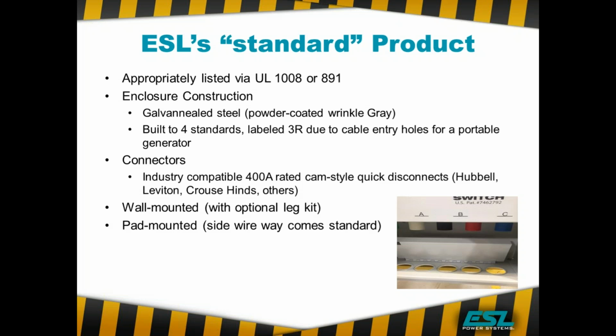Your pad mounted units come standard with a side wireway to bottom feed, since with most pad mounted units the conduit is going to come in the bottom. The unit still can be accessed for conduit on the back and the side and the top and other places, but the majority of them we found are bottom, so we just make that capability standard on the units.